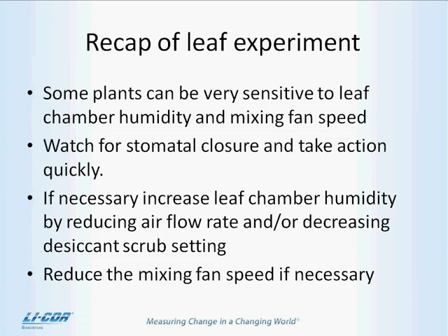Start by using a leaf chamber humidity that is a little bit above ambient to compensate for the compressed boundary layer because of the higher wind speeds employed. And if necessary, increase leaf chamber humidity and reduce chamber mixing fan speed to increase the boundary layer thickness.